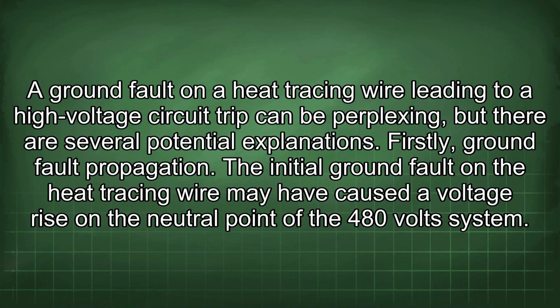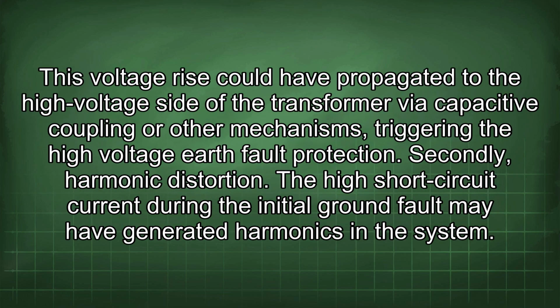A ground fault on a heat tracing wire leading to a high voltage circuit trip can be perplexing, but there are several potential explanations. Firstly, ground fault propagation. The initial ground fault on the heat tracing wire may have caused a voltage rise on the neutral point of the 480 volt system. This voltage rise could have propagated to the high voltage side of the transformer via capacitive coupling or other mechanisms, triggering the high voltage earth fault protection.